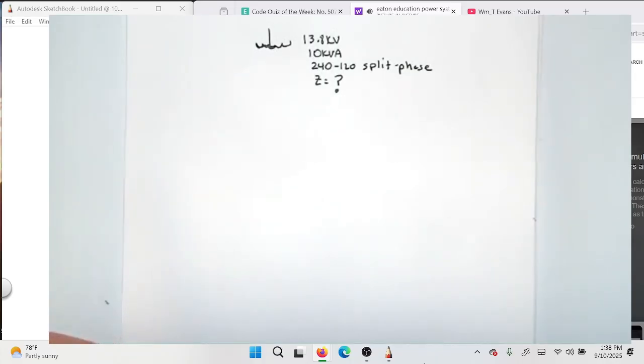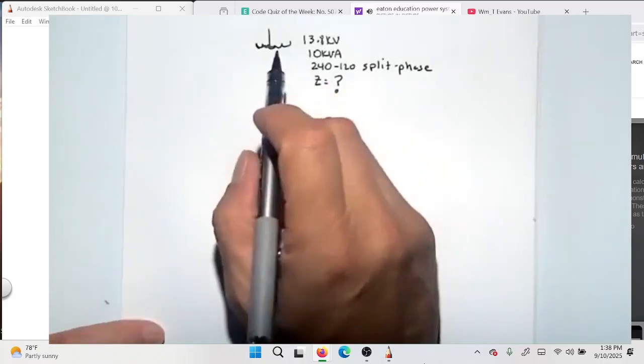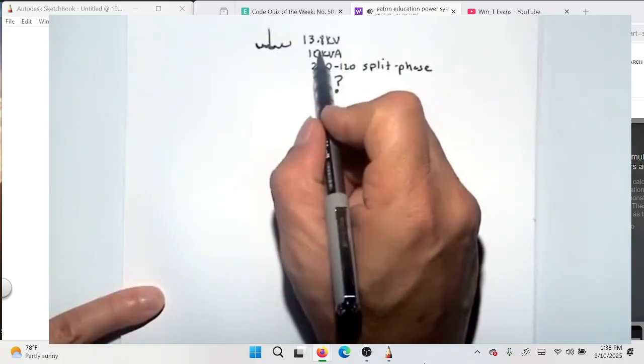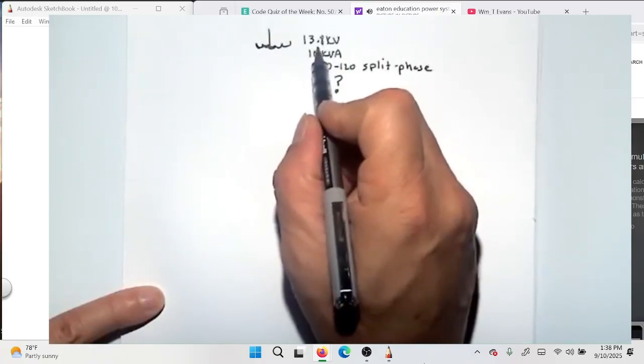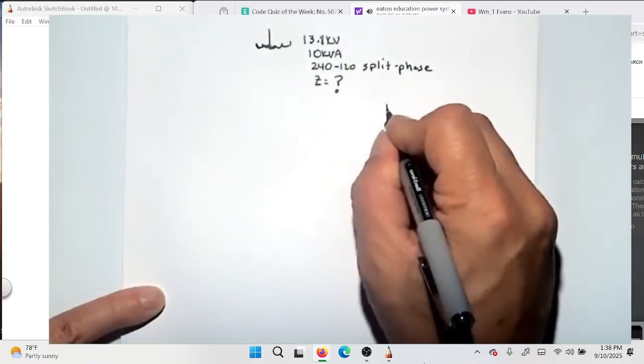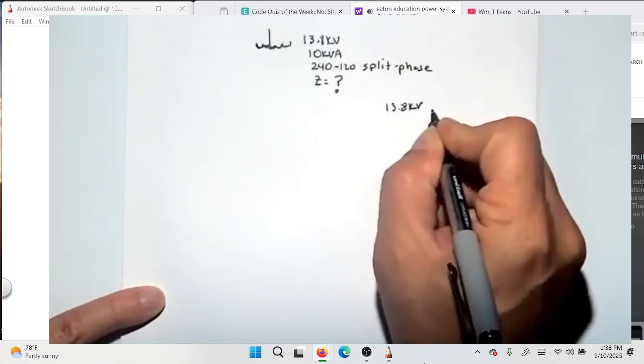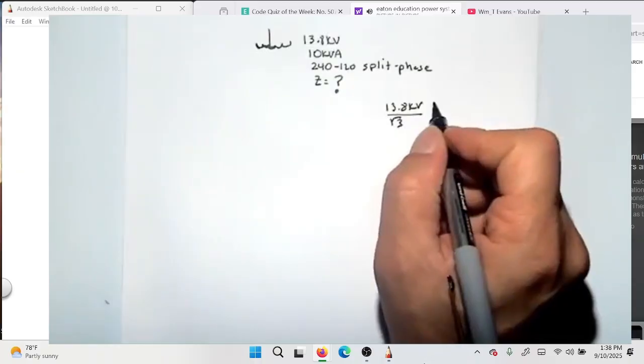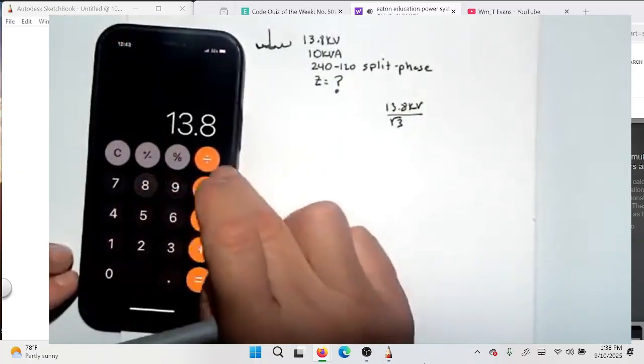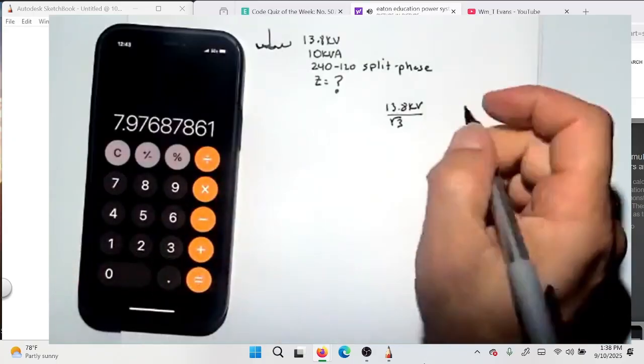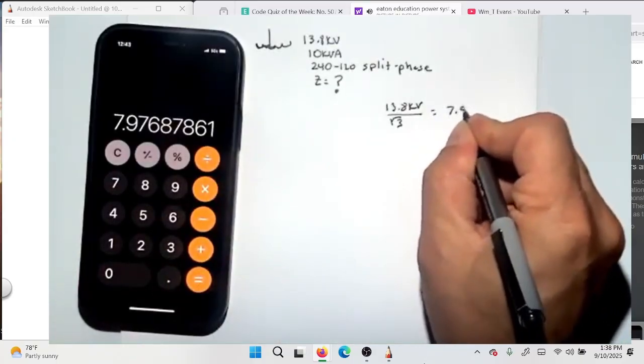Okay, now this is a fun one because this is what's outside your house. And you want to think a little bit about what's the full load amps on the primary and secondary on this transformer. I didn't draw the secondary here because I want to show you something. This is 13.8, typically line to line, or it could be line to neutral, which is this number divided by the square root of 3. And so if we knew the primary voltage, let's say 13.8 kV, and we divide by the square root of 3, we would get 13.8 divided by 1.73, 7.97. So that would be our kV on the primary side, okay?